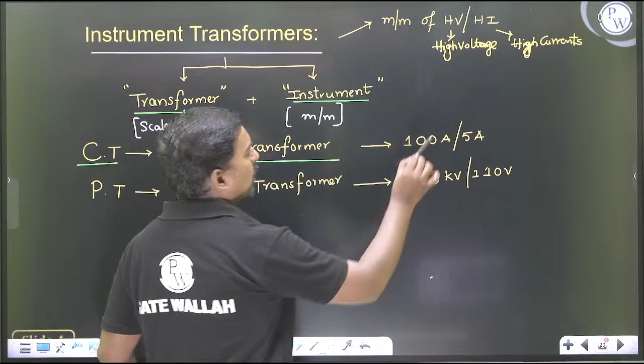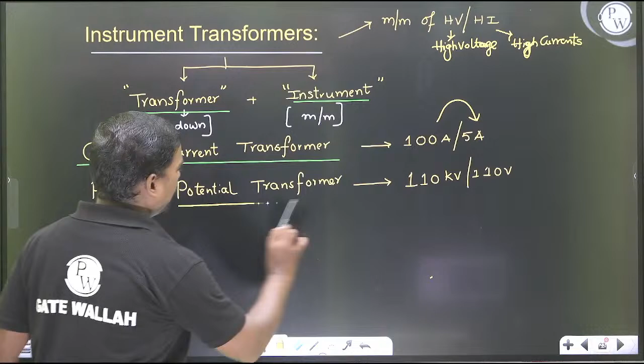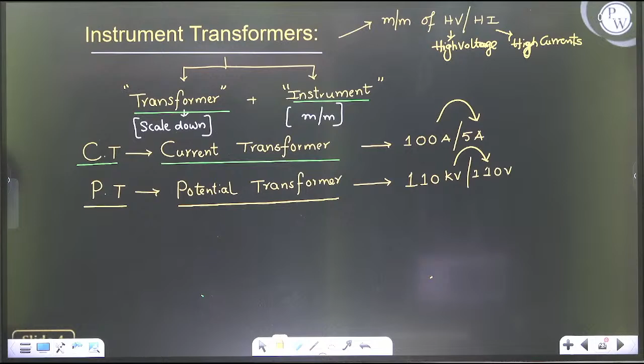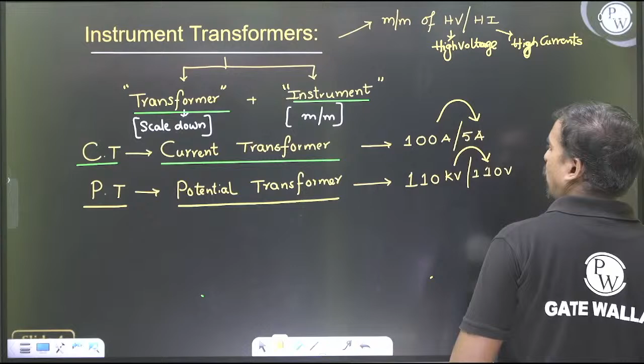A current transformer will convert 100 amperes to 5 amperes. Next, PT, also called the potential transformer, is suitable to convert 110 kilovolts to 110 volts. After that, we will go for the measuring instrument.